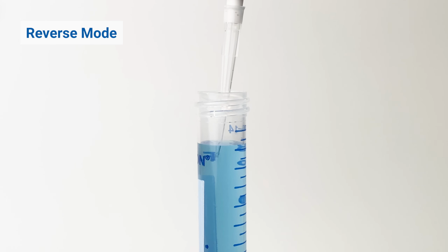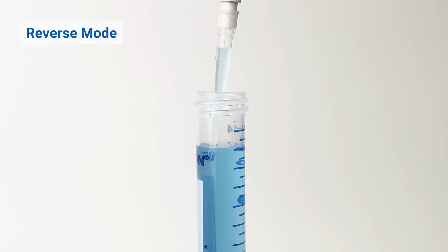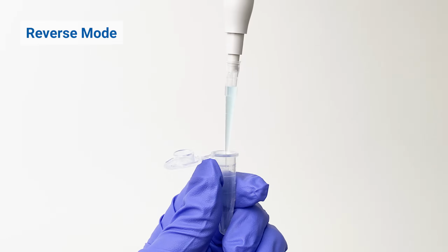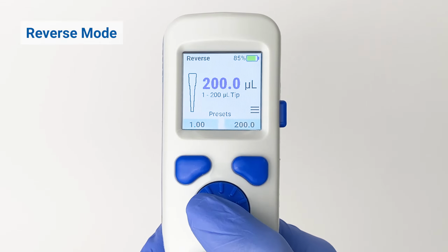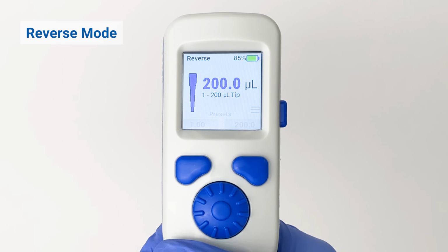Reverse mode allows users to mimic the functionality of a positive displacement pipette. Extra volume will be aspirated into the pipette tip, and the exact target volume will be dispensed. Aspirating and dispensing can be performed similarly to standard mode, but an additional purge step must be performed manually.